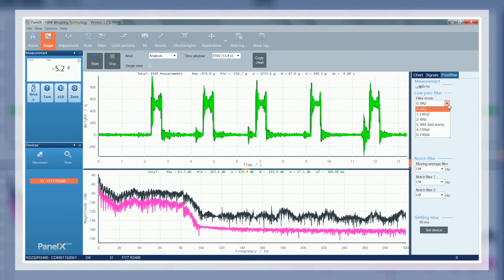A suitable low-pass filter is selected first. There are several filter modes available for the selection of the low-pass filter. Filter mode 5 has proven to be useful for Checkweigher applications because it's a fast FIR filter. Panel X will also calculate the frequency spectrum of the raw signal for us. The frequency spectrum may help in the detection of interfering frequency in the immediate vicinity of the Checkweigher. Frequencies above 5 to 10 Hz typically do not contribute to the useful signal and only produce noise.